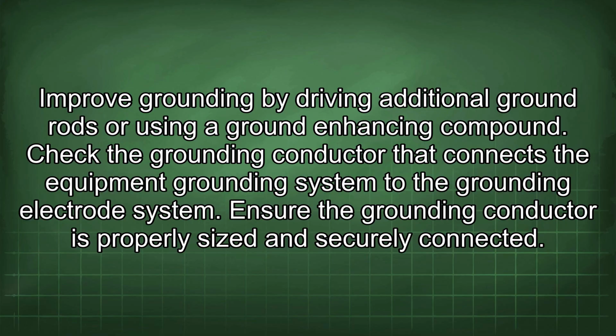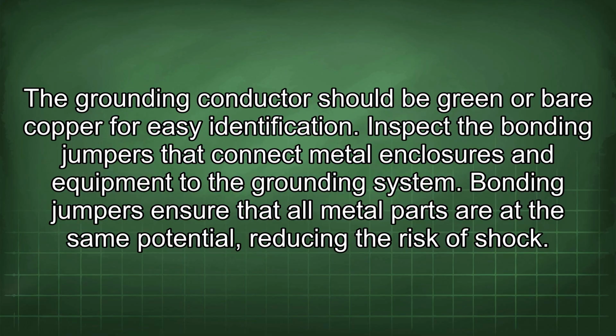Check the grounding conductor that connects the equipment grounding system to the grounding electrode system. Ensure the grounding conductor is properly sized and securely connected. The grounding conductor should be green or bare copper for easy identification. Inspect the bonding jumpers that connect metal enclosures and equipment to the grounding system. Bonding jumpers ensure that all metal parts are at the same potential, reducing the risk of shock.